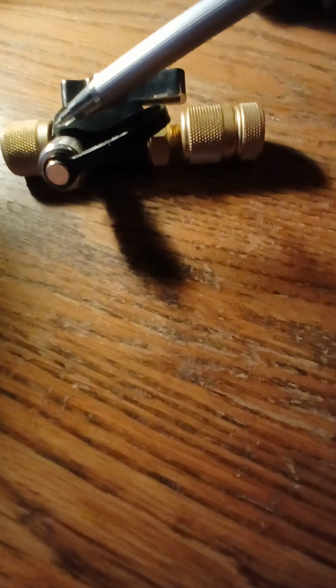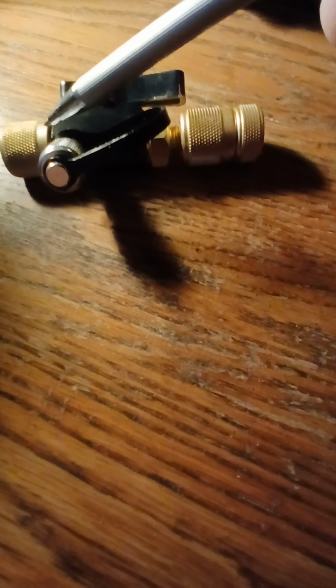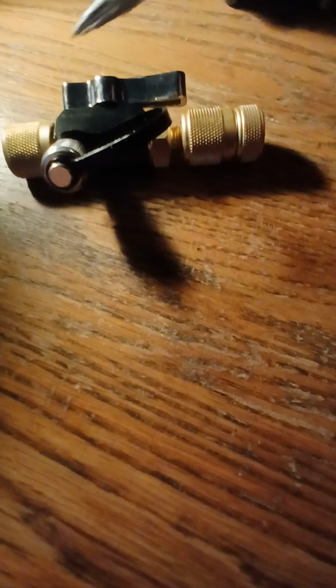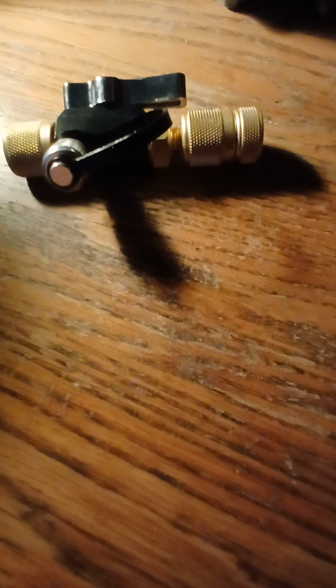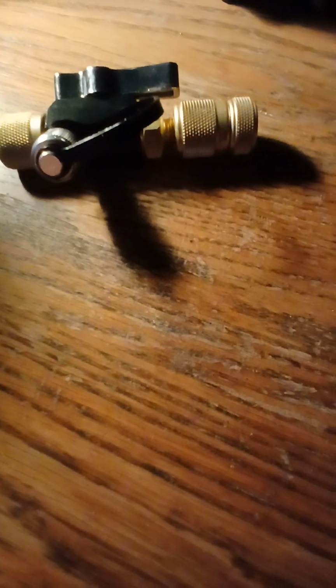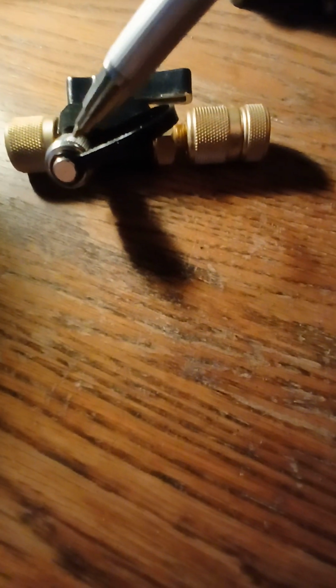But this either charging, pressure port, or vacuum port here could be used, and I'm thinking the reason it's in the front is perhaps to keep pressure at all times. So you would need to keep continuous pressure on it if you're working on it. Say, for instance, if you're pulling a vacuum or somewhat thereabouts.